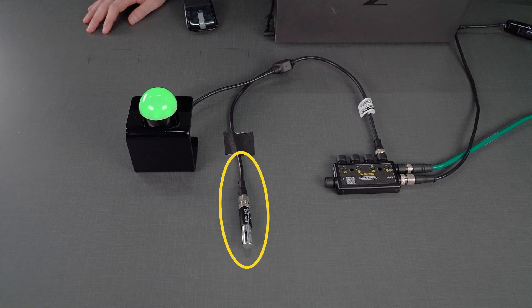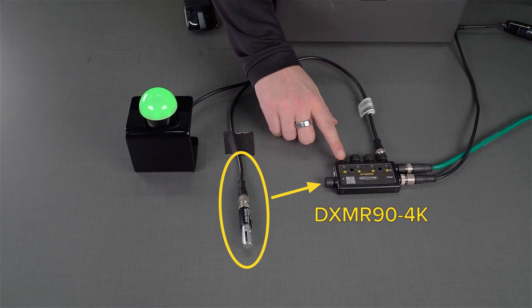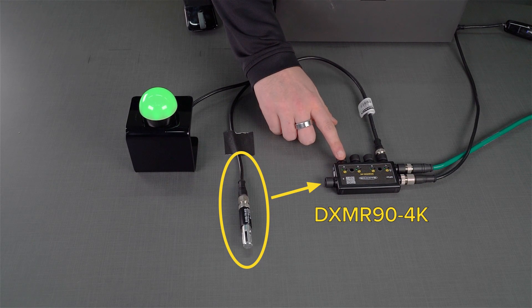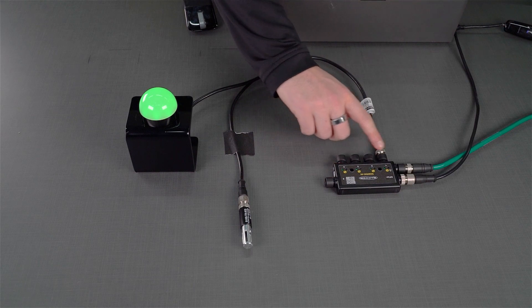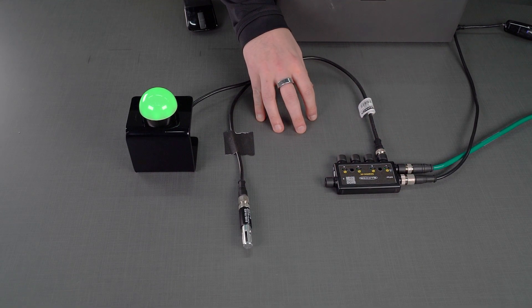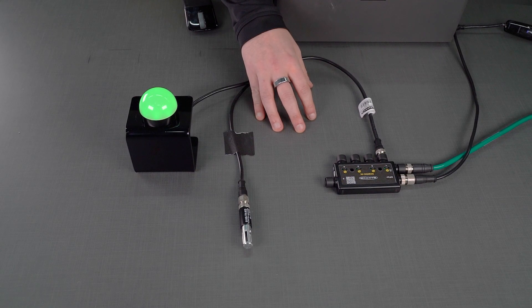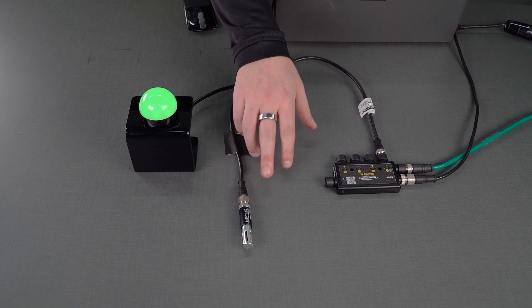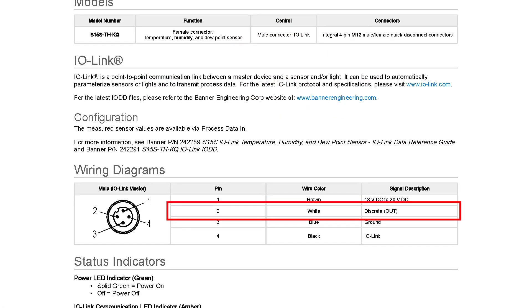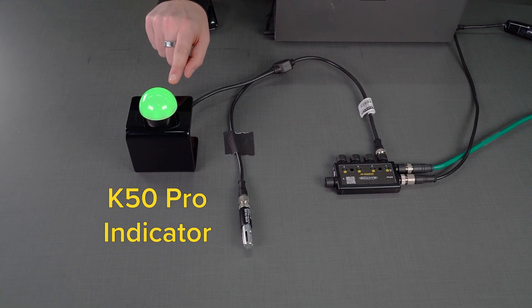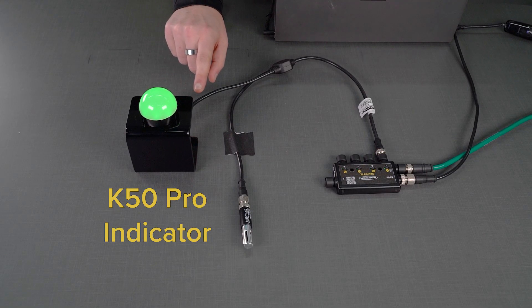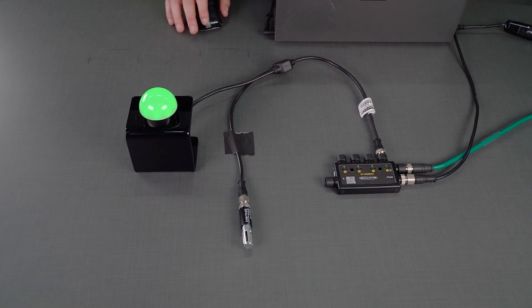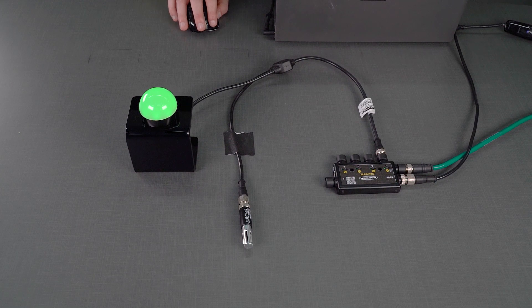Here we have it connected to an IO-Link Master, the DXM R90 4K IO-Link Master. And via that IO-Link Master we're connected to our PC via an Ethernet cord set. An interesting thing about this sensor is the ability for it to turn on a discrete output on the sensor itself on pin 2, which is the white wire. What we have here is a K50 light that can be actuated via that discrete output on pin 2 on that white wire that's connected to the IO-Link device.